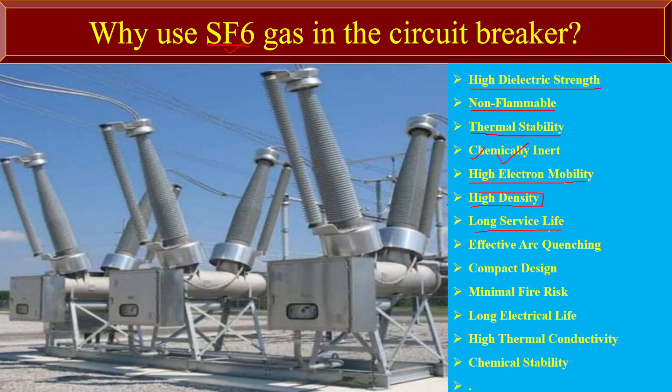SF6 has excellent arc quenching properties due to its ability to rapidly absorb free electrons that dissociate during electrical arcing. These characteristics help in extinguishing electrical arcs that occur when a circuit breaker interrupts a high current flow.